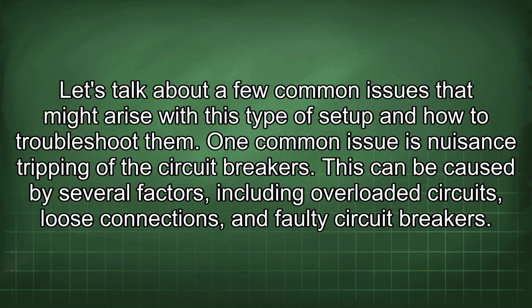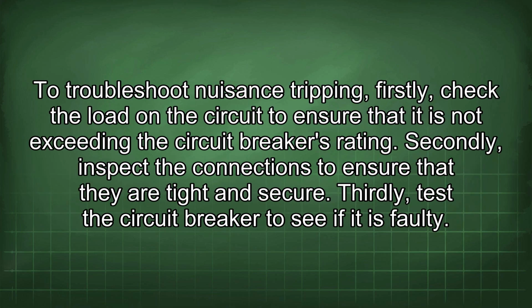Let's talk about a few common issues that might arise with this type of setup and how to troubleshoot them. One common issue is nuisance tripping of the circuit breakers. This can be caused by several factors, including overloaded circuits, loose connections, and faulty circuit breakers. To troubleshoot nuisance tripping, firstly, check the load on the circuit to ensure that it is not exceeding the circuit breaker's rating. Secondly, inspect the connections to ensure that they are tight and secure. Thirdly, test the circuit breaker to see if it is faulty.